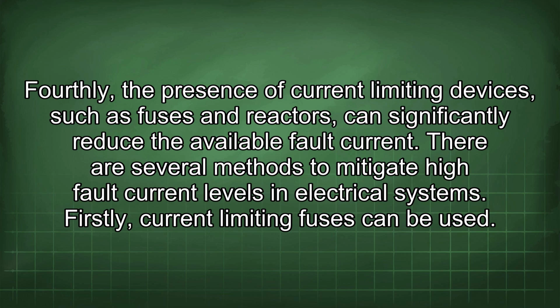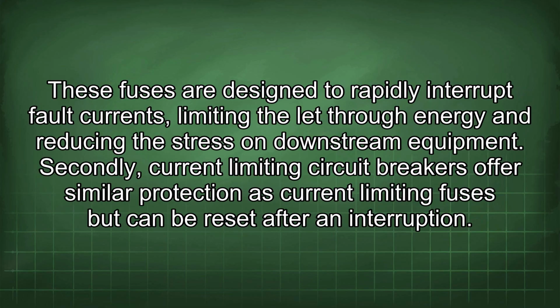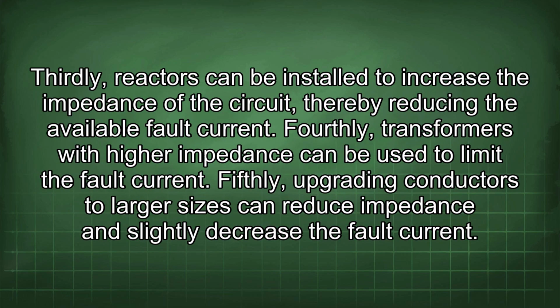There are several methods to mitigate high fault current levels in electrical systems. Firstly, current limiting fuses can be used. These fuses are designed to rapidly interrupt fault currents, limiting the let-through energy and reducing the stress on downstream equipment. Secondly, current-limiting circuit breakers offer similar protection as current-limiting fuses but can be reset after an interruption. Thirdly, reactors can be installed to increase the impedance of the circuit, thereby reducing the available fault current.